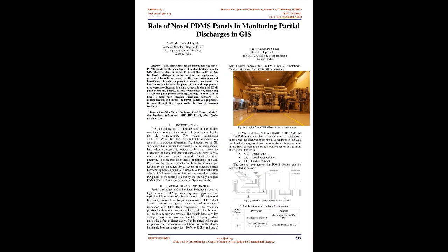Role of novel PDMS panels in monitoring partial discharges in GIS. Abstract. This paper presents the functionality and role of PDMS panels for the monitoring of partial discharges in the GIS, which is done in order to detect the faults on gas-insulated switchgears earlier so that the equipment is prevented from being damaged. The panel components and functioning of each component is clearly mentioned.